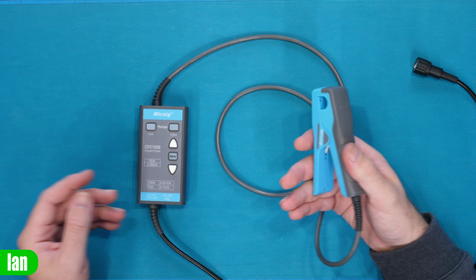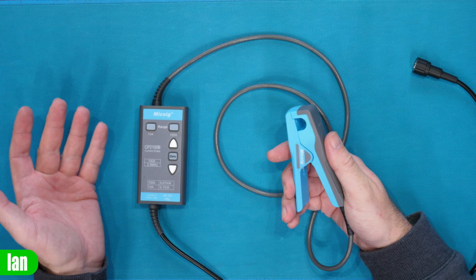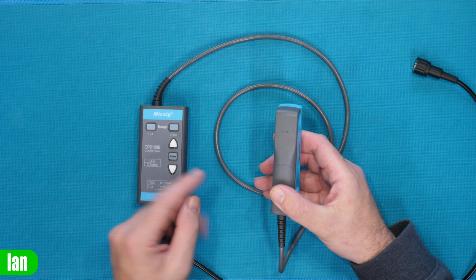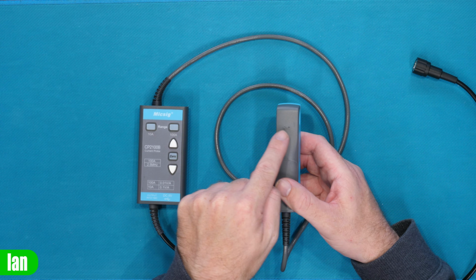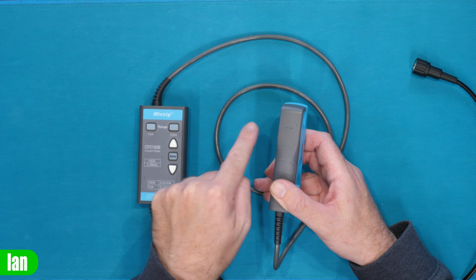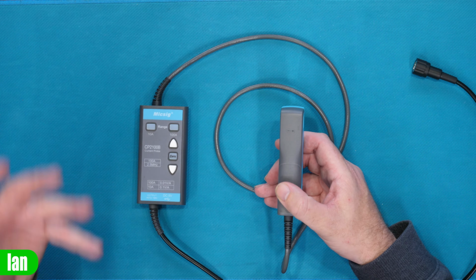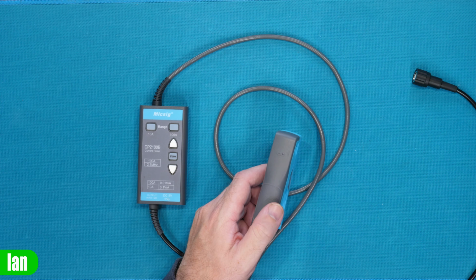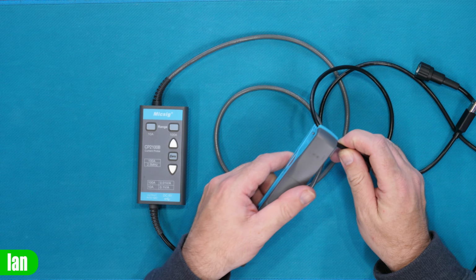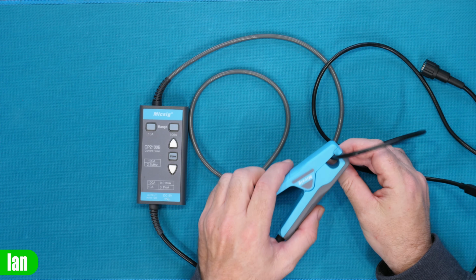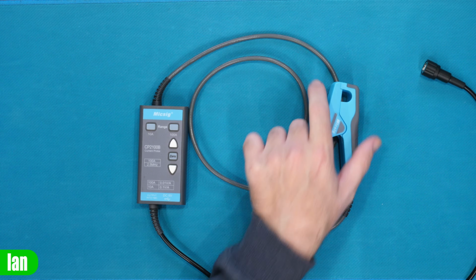It has a nice spring action and can cope with cables up to 13 mil. Something to note on this clamp is it is directional, so you'll see printed on the top here an arrow of direction, so you need to make sure when you're clipping it onto your cable, you do have it for the correct direction of current travel. So again, you can simply clip it onto a cable like that for doing the current measurement.